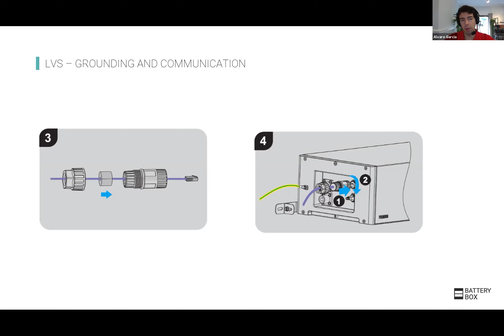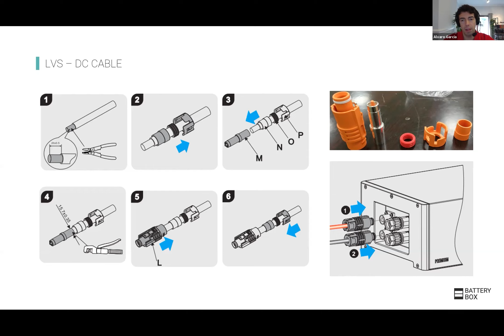And then we get to the connectors. In the future, we would offer you the possibility of buying pre-made cables. But for now, you just have this simple process where you need a hydraulic crimping tool or a manual crimping tool that squeezes the connectors onto the cable. You can prepare this in advance, so when you get to site it will take just a second. You just clip the connectors right in, and from this it will go to the power on the DC side or the battery side on the inverter.